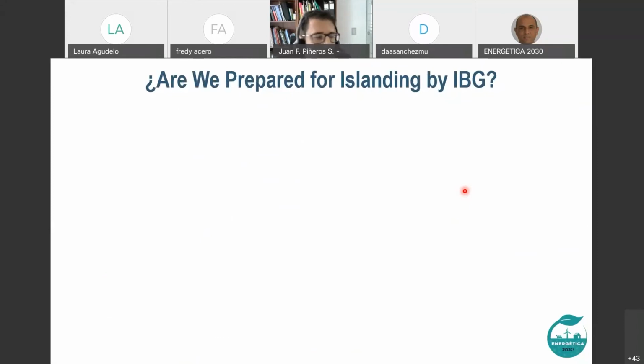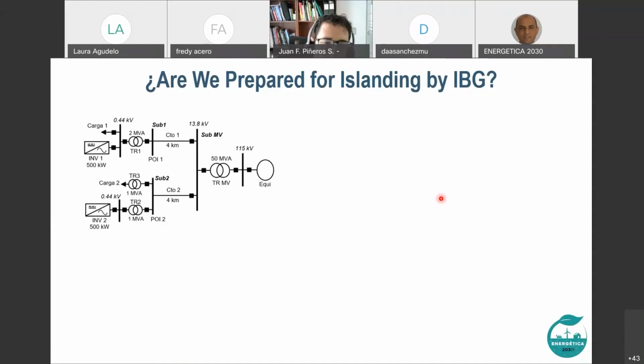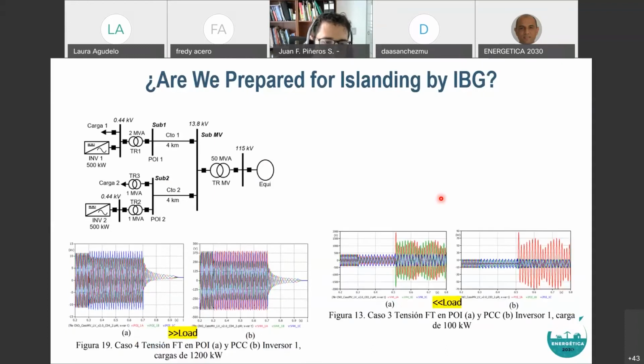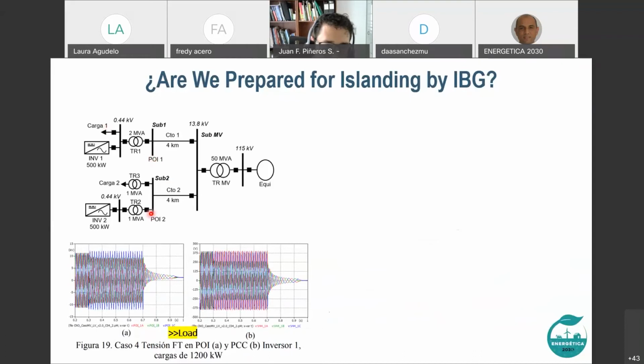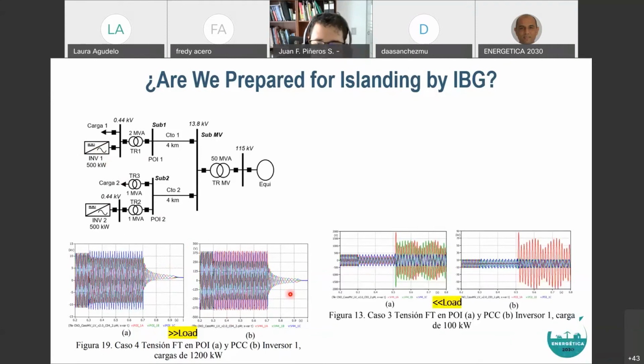Another important topic is: are we prepared for islanding? Islanding in systems with inverter-based generation. We were simulating this in the network as well. In the first case, the load of the network is much higher than the inverter-based generation. Of course, the low voltage will immediately trip the inverters, and there is no problem. When the load is much lower in comparison with the inverter-based generation in this network, the natural result is overvoltage, which we know is handled by the protection of the inverters, specifically the DC bus overvoltage, which will trip them. This is normally not a problem.